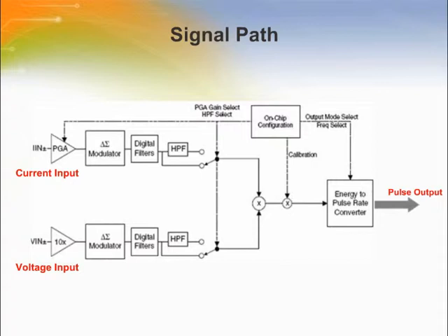The single bit data is passed to the low pass decimation filter and outputs at a fixed word rate. A digital high pass filter removes any DC components from the selected signal path. After filtering, the instantaneous voltage and current digital codes are subjected to offset or gain adjustments. The digital instantaneous voltage and current data is then processed further. The calibrated energy value is then converted into a pulse output stream with average frequency proportional to the measured energy.